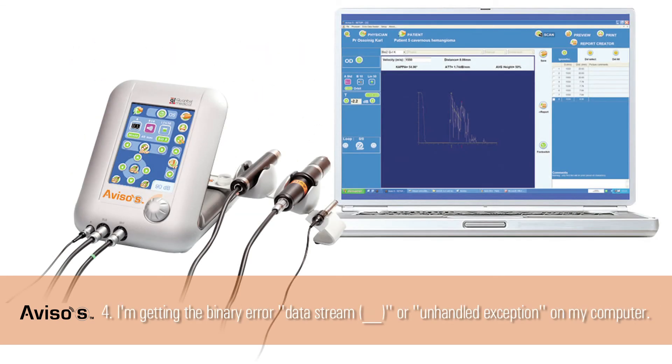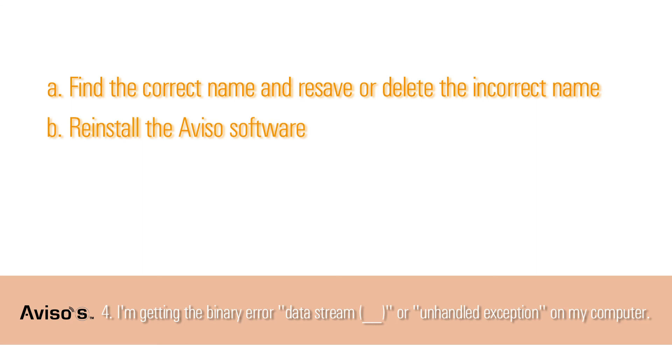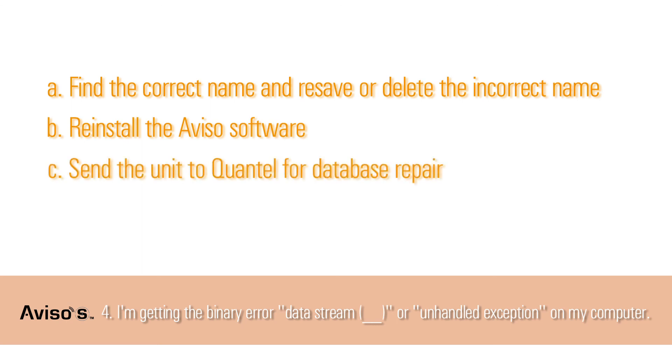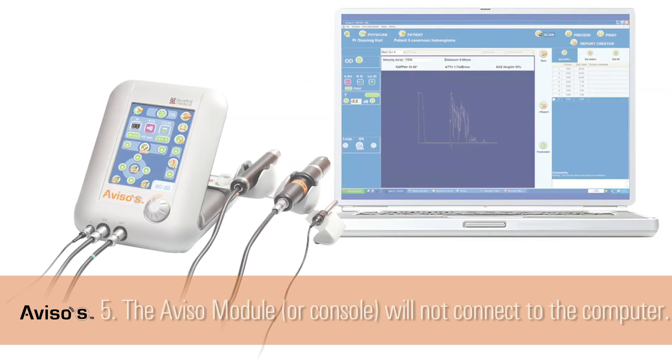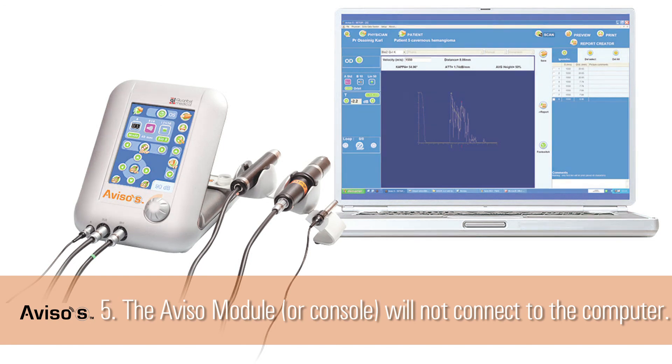Question 4: I'm getting the binary error, data stream or unhandled exception on my computer. This is likely due to a corrupt patient database, frequently caused by first, last name conflicts or a deleted name from the records. It can sometimes be resolved by finding the correct name and resaving or deleting the incorrect name. A new installation of the Aviso software may also be a solution. In some cases, you may need to send the unit to Quantel for database repair. Question 5: The Aviso module or console will not connect to the computer.